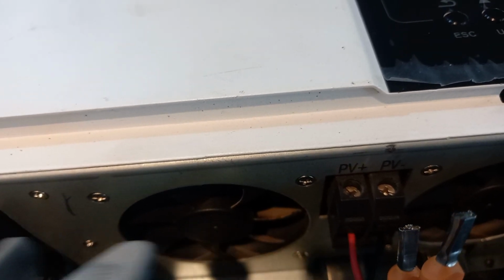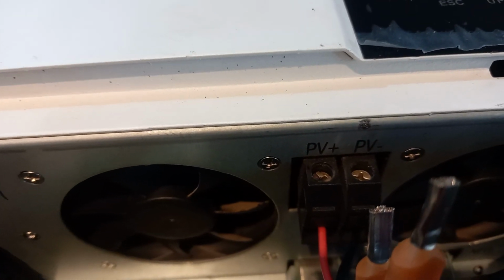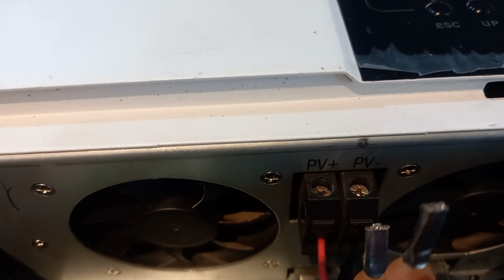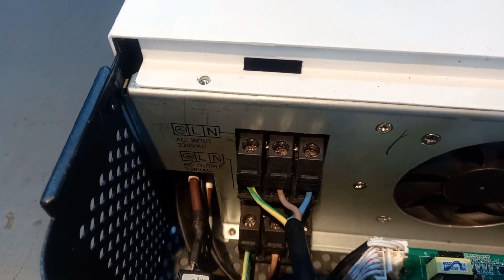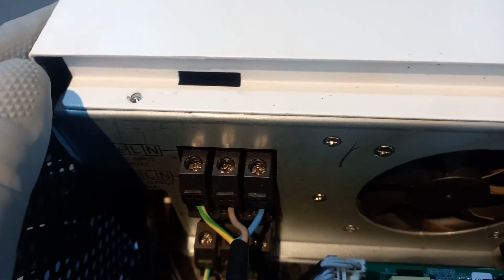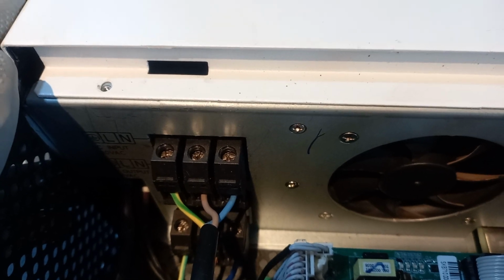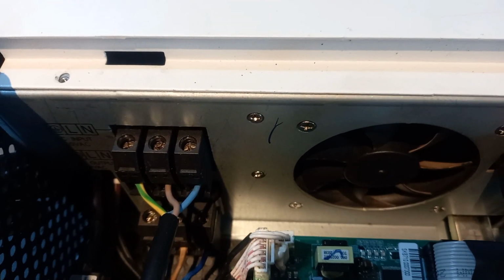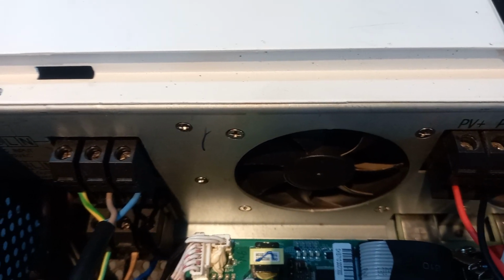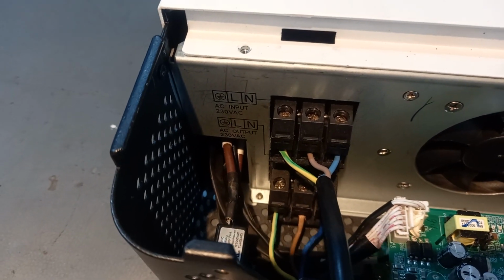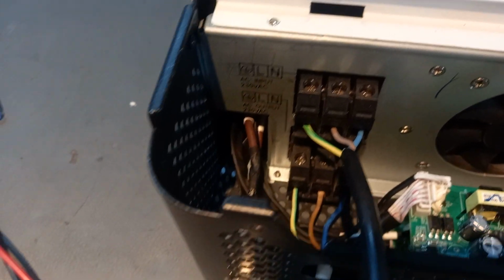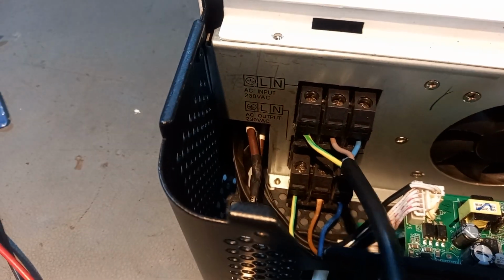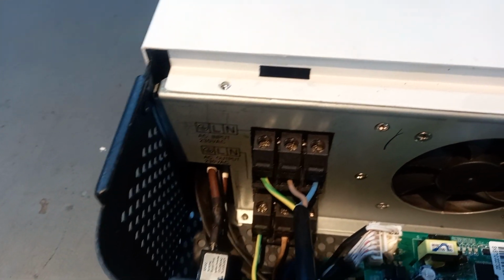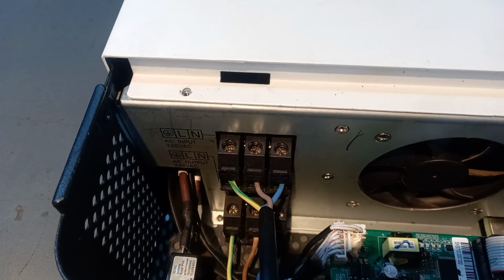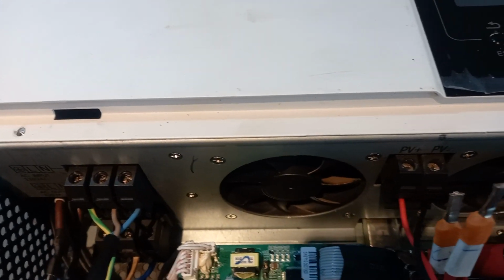Please make sure that when they connect or disconnect the inverter, they switch off the power. There must be no power at all. Same with the Eskom and the output. There must be no power. They have to make sure that the inverter is not live when connecting, because if you do that, you can damage the inverter immediately. And also here, they have to make sure that they don't swap the output with an input. So if they, for instance, take the Eskom line and connect it at the bottom, they're going to blow the inverter immediately. So just make sure of that.